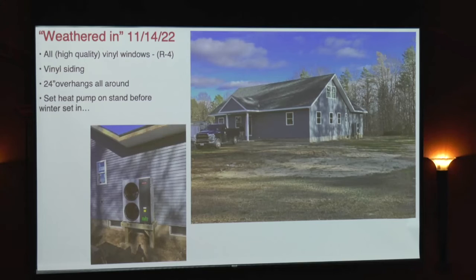One is snow. Secondly, when these units defrost, the frost will build up on that outdoor coil, and when they defrost, they can drop a quart or 2 of water, and if that water just sits on the ground or sits on a pad, it will start to form like an ice bathtub under the heat pump. And pretty soon that water will actually start to go up into the cabinet of the heat pump, and I do know of a case where the coil actually was ruptured. The outdoor refrigerant coil was ruptured due to ice expansion. So get the units up above the snow, above the ground, above the insects, the grass, the leaves, and so forth. I would suggest at least a foot, and if you're in a deep snow area, maybe even a couple feet. This unit is up at least a couple feet above finished grade here.